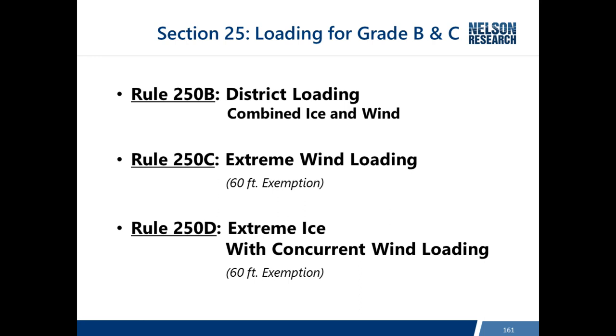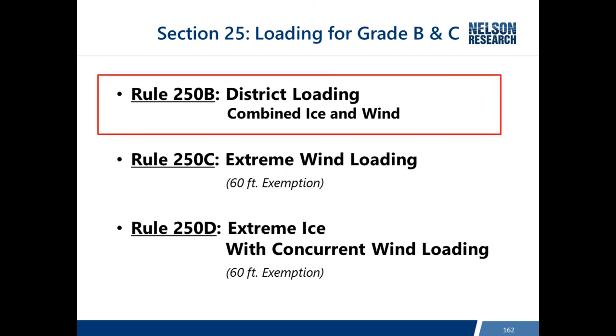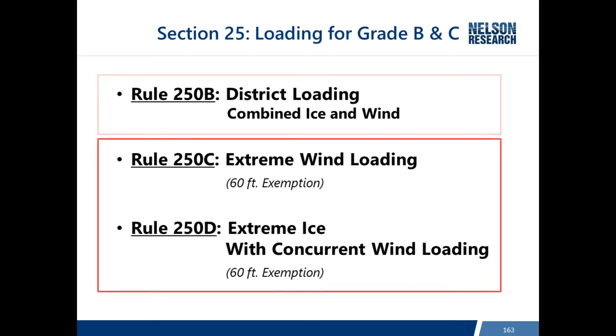In Section 25, covering loading, there are three different load cases. Rule 250B is the district loading, which applies to poles of all lengths and is defined as combined ice and wind loading — most distribution is governed by Rule 250B. When poles are taller than 60 feet above ground, Rules 250C and 250D also need to be considered. Rule 250C is extreme wind with no ice, whereas 250D is extreme ice with concurrent wind.